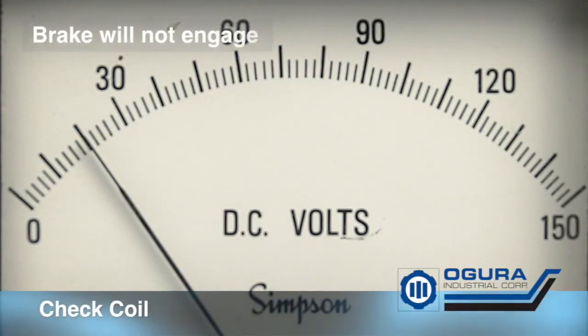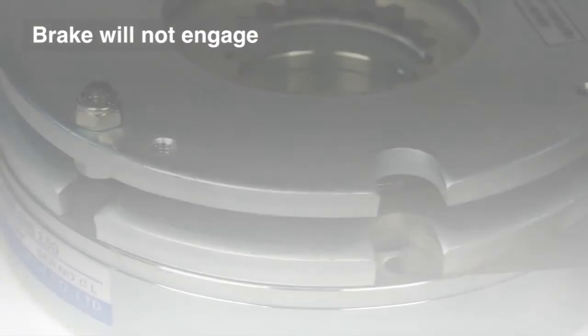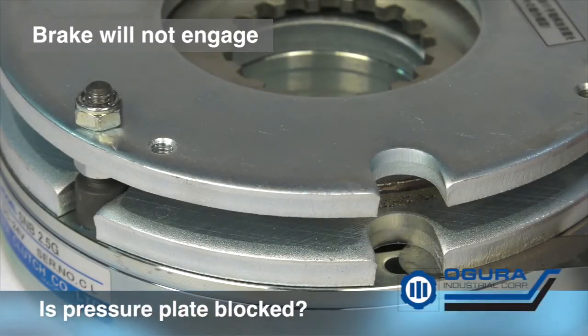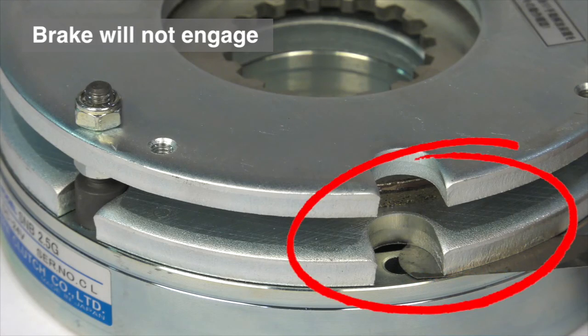Brake will not engage. Check the voltage to make sure voltage is being turned off to the brake. Make sure pressure plate is not blocked. Check to make sure there is nothing stuck in the brake blocking the brake or make sure there are no release screws tightened down.